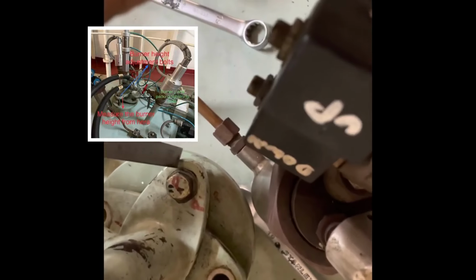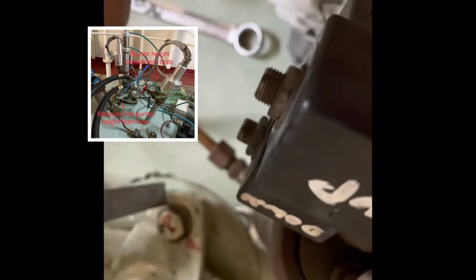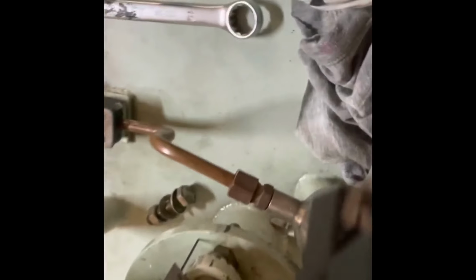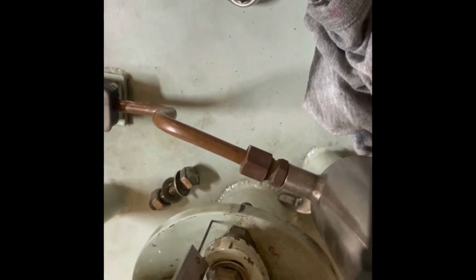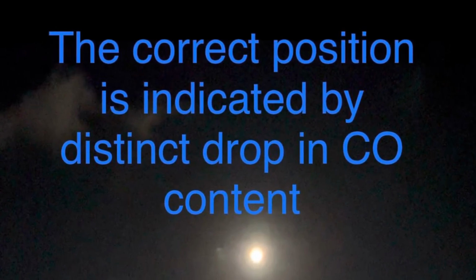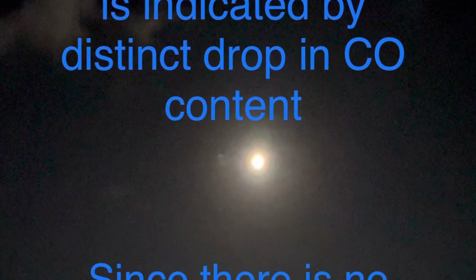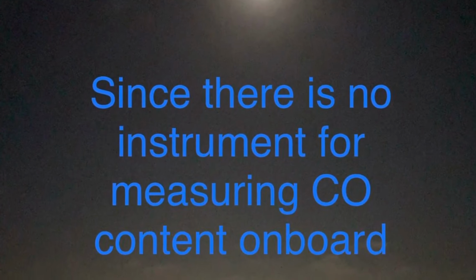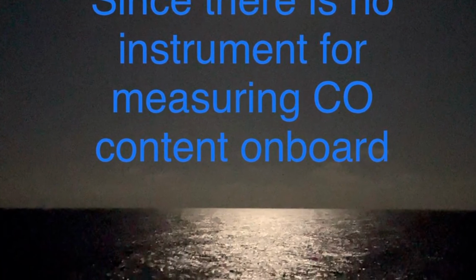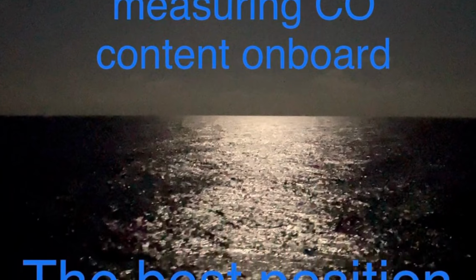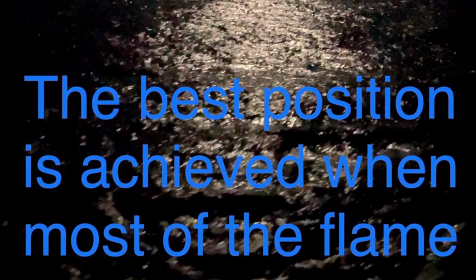Before opening the burner, check the burner distance. I would like to say something about this burner distance. The distance is not fixed. You can adjust it according to the IGG CO content. The correct position is indicated by a distinct drop in measured CO content. Since there is no instrument for measuring CO content on board, the best position is achieved when most of the flame burns clear or blue.